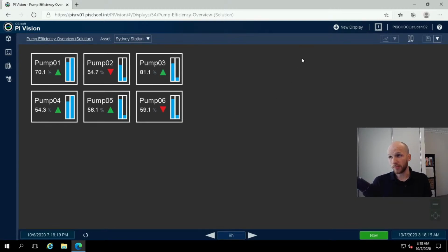And we see a bunch of pumps. We actually see the temperature and pressure, the bearing temperature, and I think that is the flow rate in the second dial there. But more importantly, we see these numbers, which are the current operating efficiencies of each pump, and whether they are above or below the expected, the nominal efficiency, or our level we've set that is desirable efficiency for these specific pumps operating at these specific power.